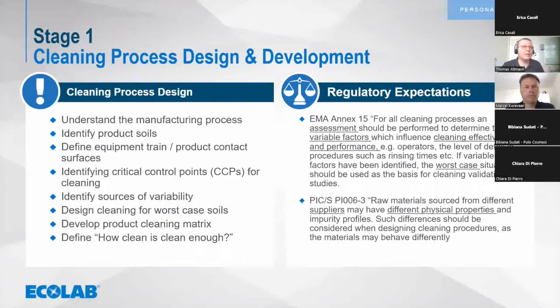If I understand these, I can also make my validation much more useful to the practical world, to say I need this kind of 80 degrees temperature for, let's say, lipstick removal, like these everlasting lipsticks which need a high temperature. If I do not get to that temperature, I cannot clean it. That is a critical control point, and it should be added to your validation documentation that you require this temperature for a certain amount of time.